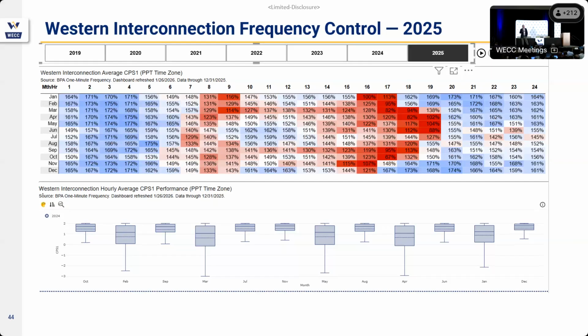I'd say it's arrested between '24 and '25 — it hasn't gotten worse. But it does raise the question: is a rolling 12-month CPS1 score an adequate reliability metric? We do have BAL, a 30-minute metric — you must operate above minus 700 for less than 30 consecutive minutes. So we have that standard, but our control is getting worse, and that's basically what the data is telling us.